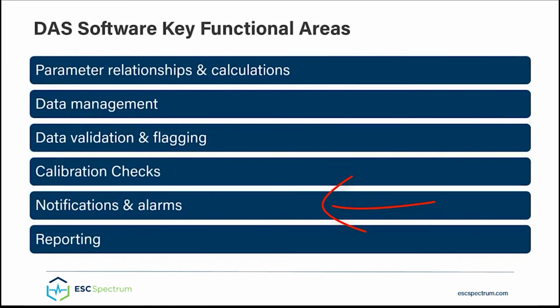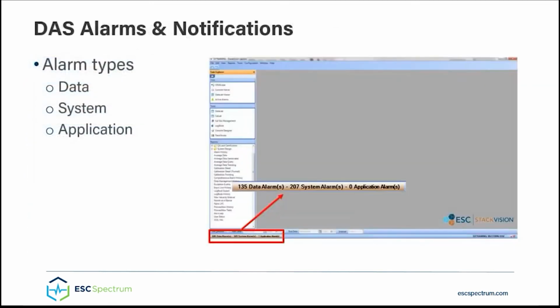Now let's move on to notifications and alarms. Your DAS should have an alarm and notification function. An alarm should be generated whenever an exception event occurs. Alarms should cover data, system, and application exception events. A data alarm example would be anything that may impact compliance, such as excess emissions or failed calibrations. System alarms would be anything that may impede your DAS operations, such as network communication errors or low disk space. And processing errors in your DAS would be an example of an application alarm.